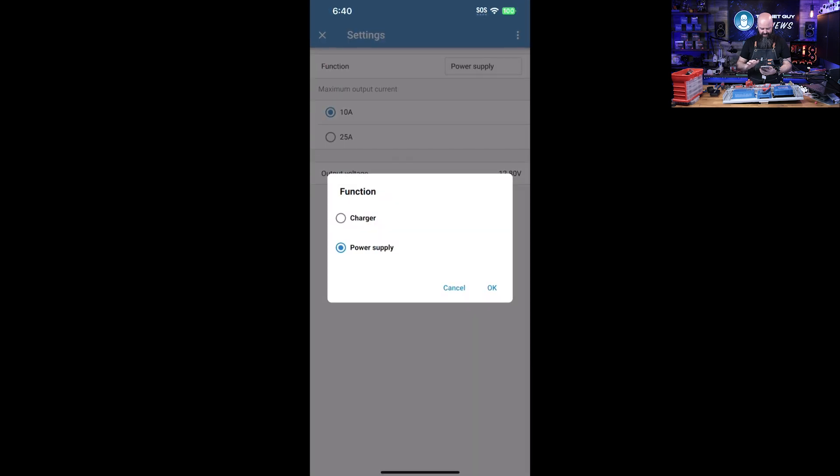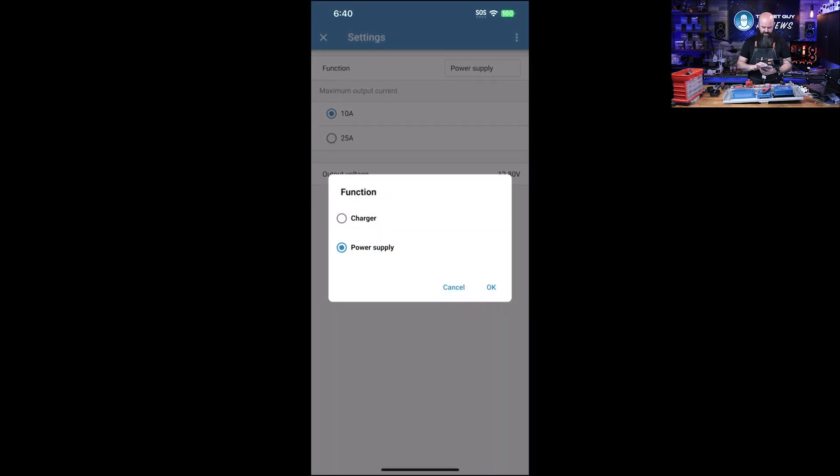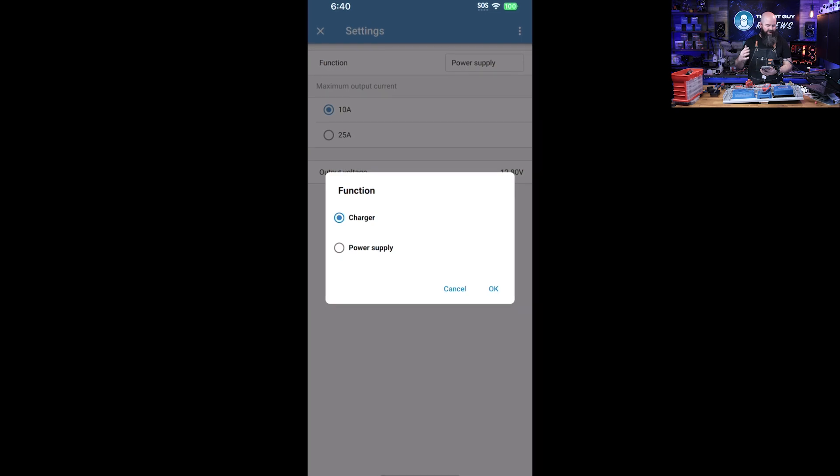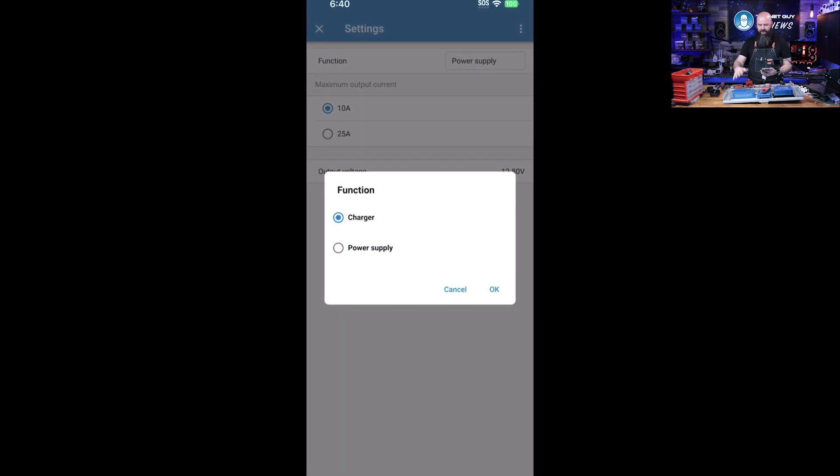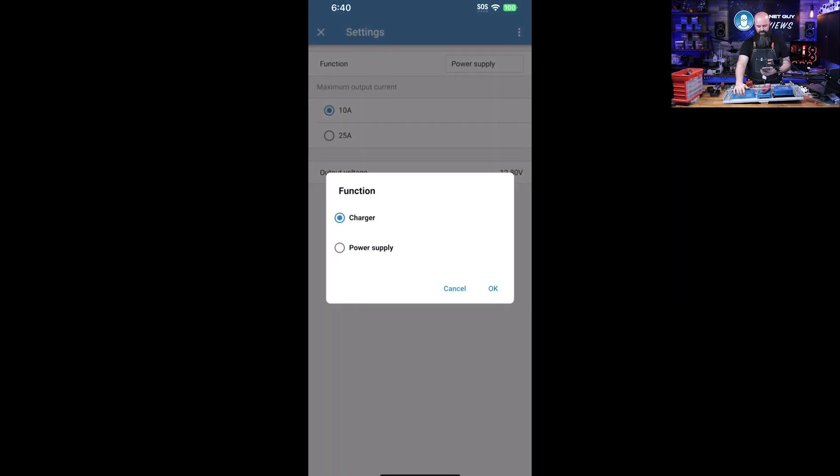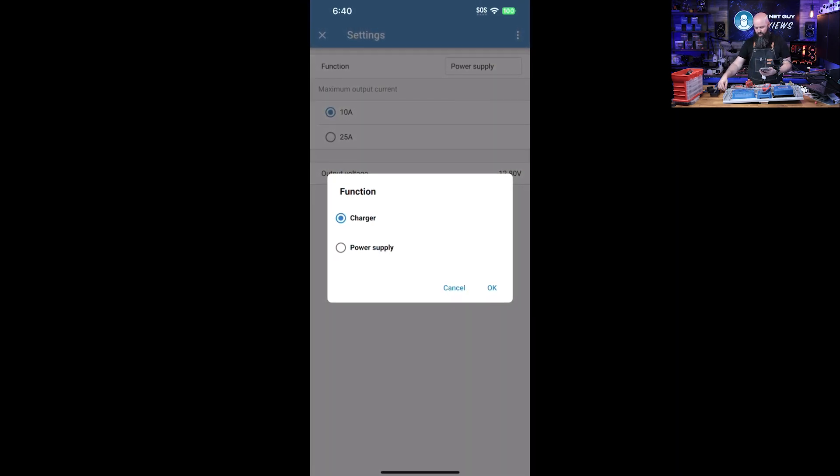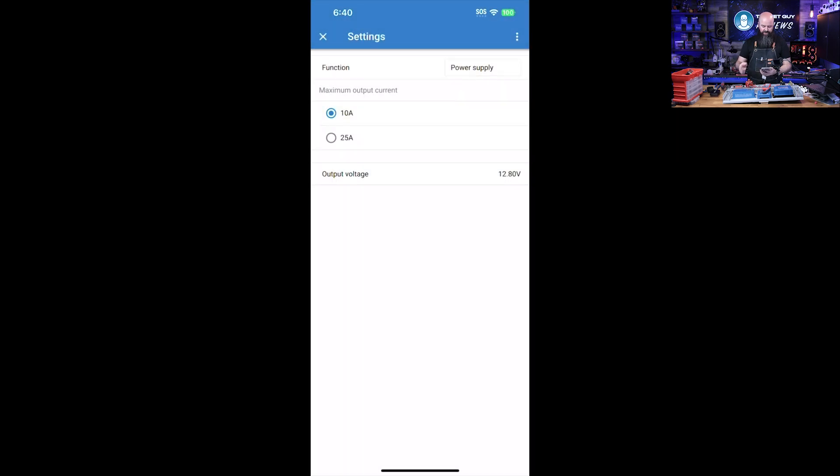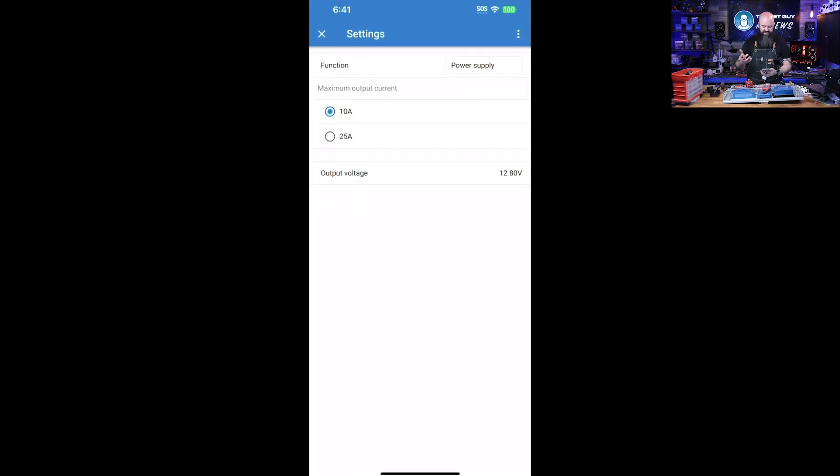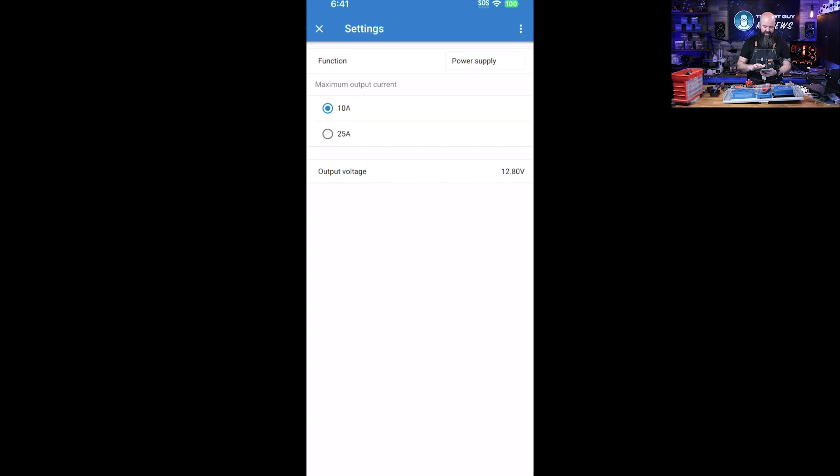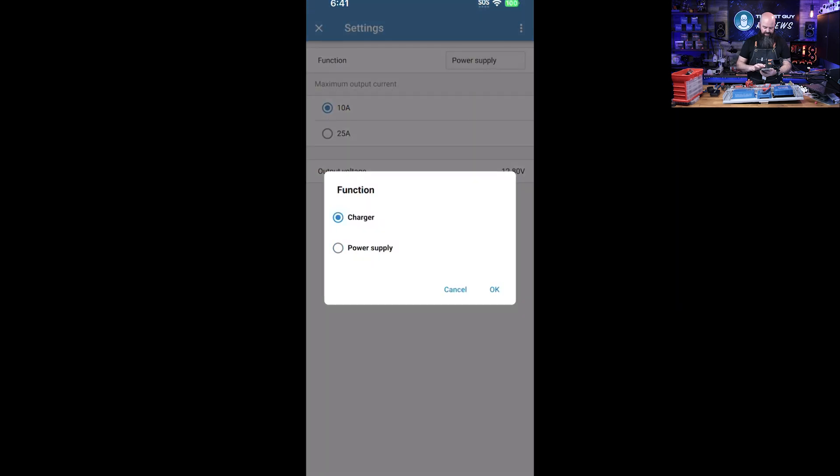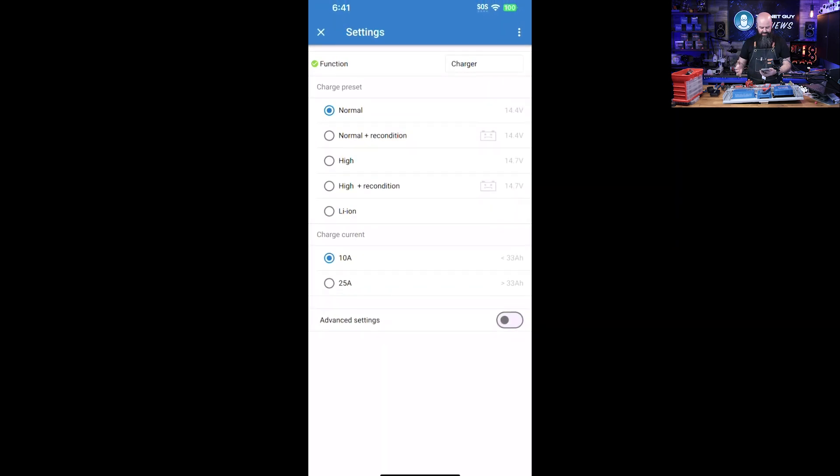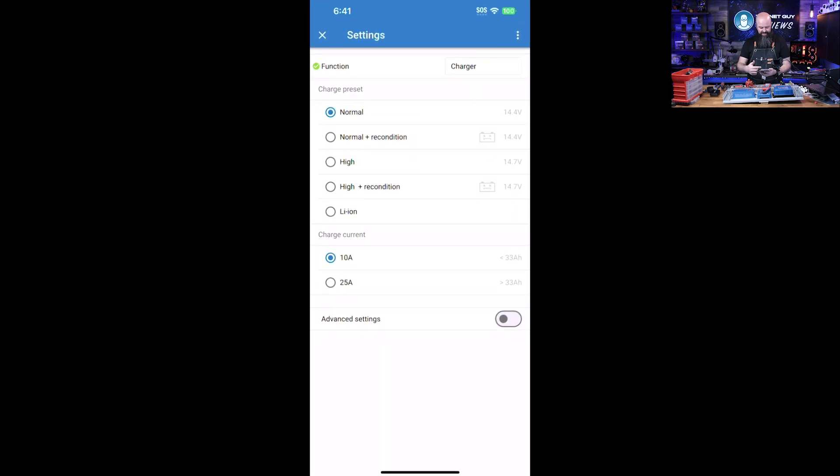You can go into charger mode which implies that you have a battery, but this can also act like a power supply. If you've got an off-grid system and you just want to have a 12-volt supply while you have AC, up to 25 amps, you can use this as a very high quality power supply. If you switch it over to charger mode, that's where the world gets more interesting.